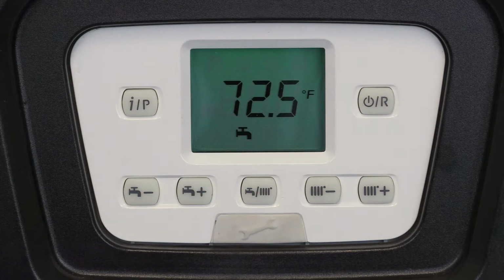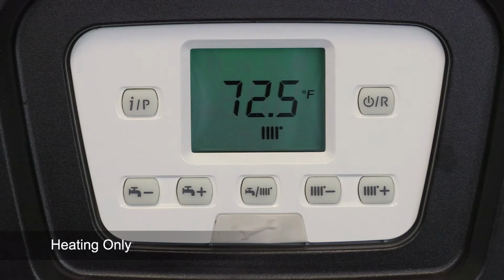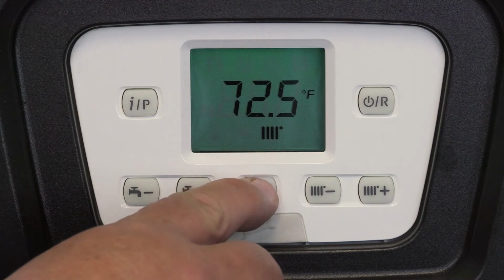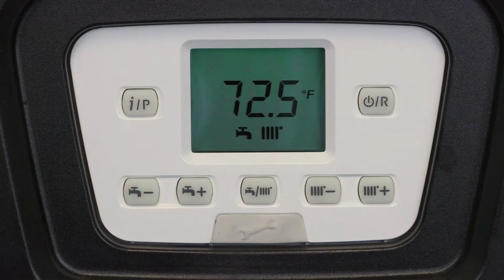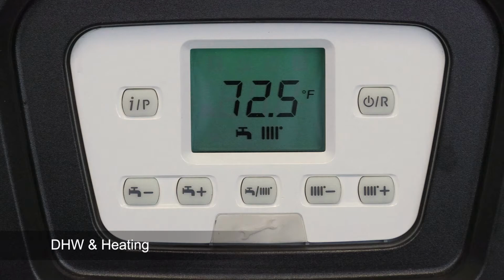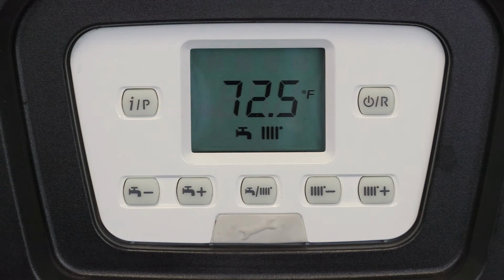Pushing the button again, the faucet icon will disappear and the radiator icon will be displayed. In this mode, the unit will only call for heat. Press the button again and both icons will appear on the display again for normal operating mode. In the instance where a customer may have inadvertently changed this setting and is no longer getting either heat or domestic hot water, check to see what mode the boiler is in.